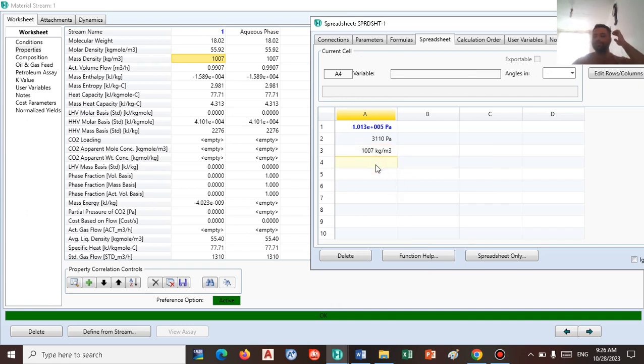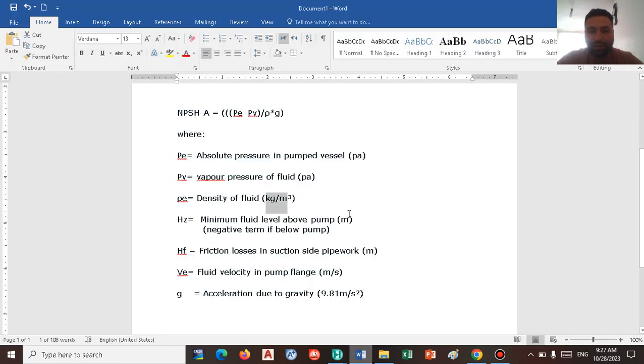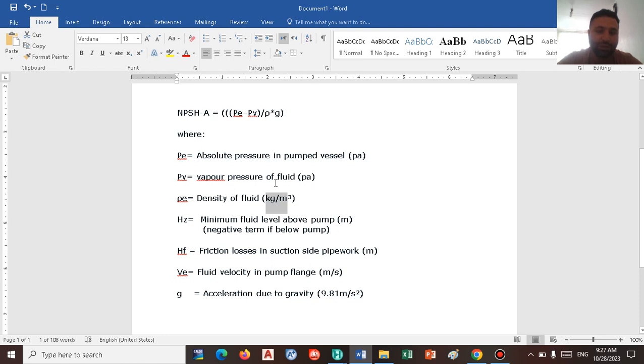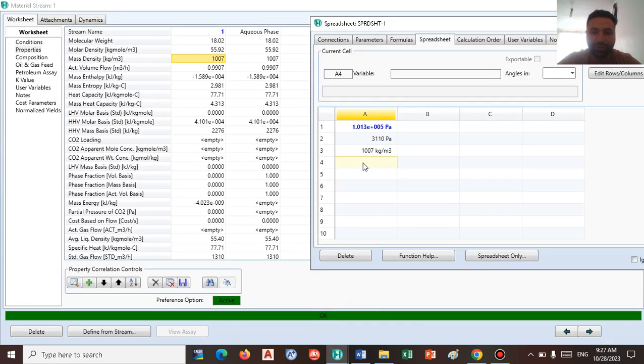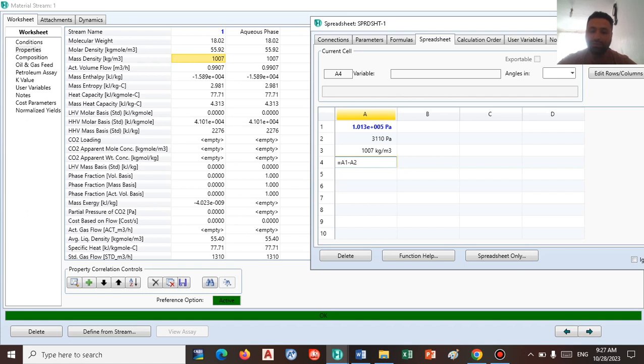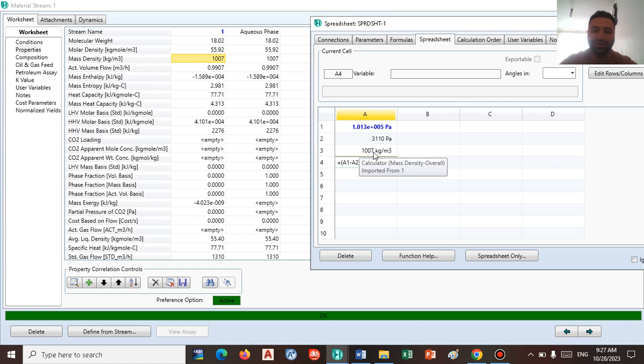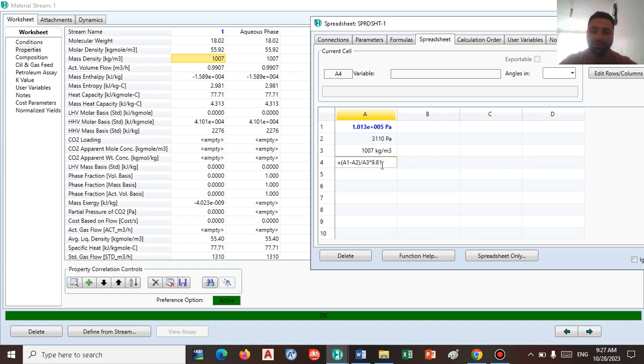So let's formulate this number and find out how HySys calculates NPSH. As we know, we have absolute pressure minus vapor pressure or bubble point pressure that we inserted to the spreadsheet divided by mass density, which is divided by mass density multiplied by acceleration due to gravity. So let's insert this number to the spreadsheet and formulate it. Just press equal, and we have A1 minus A2, divided by A3 which is the mass density, multiplied by 9.8 which is the acceleration. Press enter.